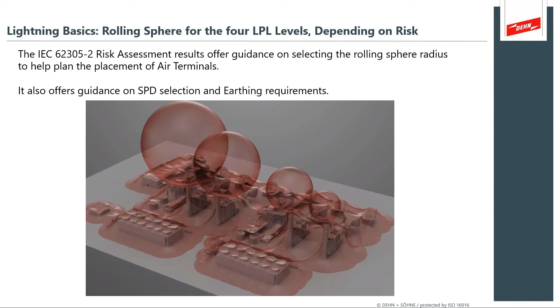As we move forward, I've got a nice illustration about the LPL rolling sphere. A less severe lightning environment has a larger rolling sphere, while a more severe environment, like a hospital full of babies and liquid oxygen, with high fire risk and difficult evacuation, has a smaller rolling sphere. This allows you to tailor the rolling sphere design to meet your need. If you're a hospital, you may have more stringent requirements than in a less severe application, and we'll see this represented when inspecting for lightning protection at our site.